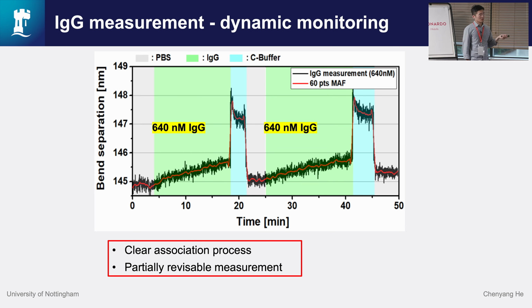This is the initial dynamic monitoring using the microfluidic setup. At the very beginning, we just pump in the PBS solution in the flow cell, and you can see it is flat, so nothing responds, which is good. And then we add the IgG into the flow cell, and we can see a very clear association process. We did the experiment twice. We can see clearly in both cycles that there is roughly 1 nanometer change due to the same concentration of IgG.